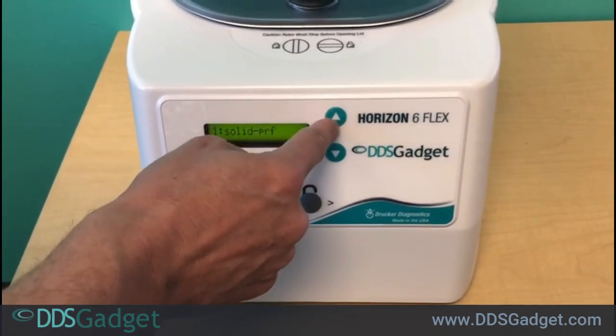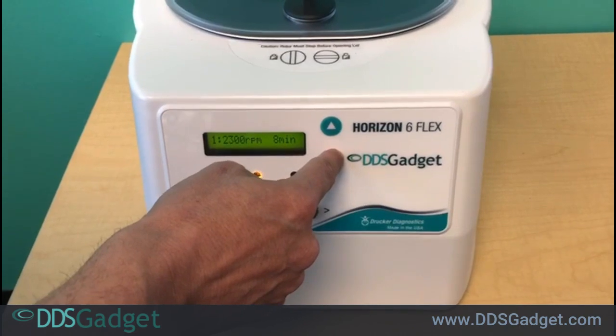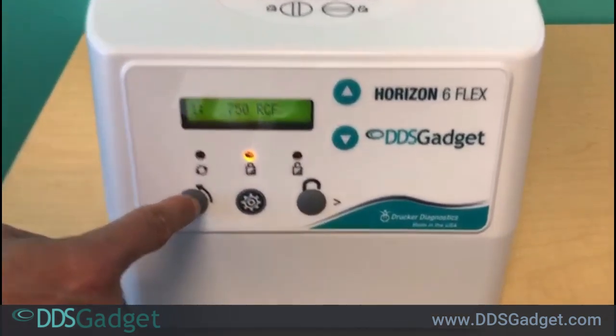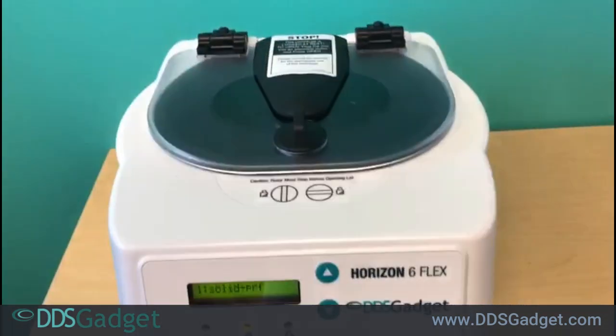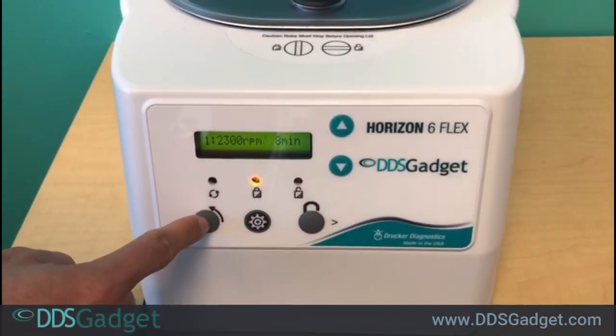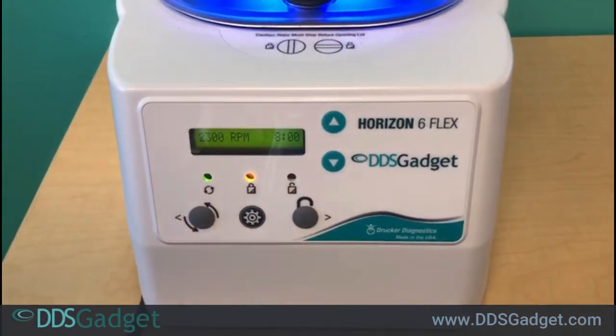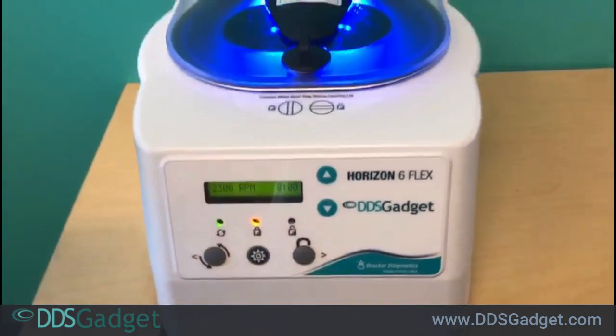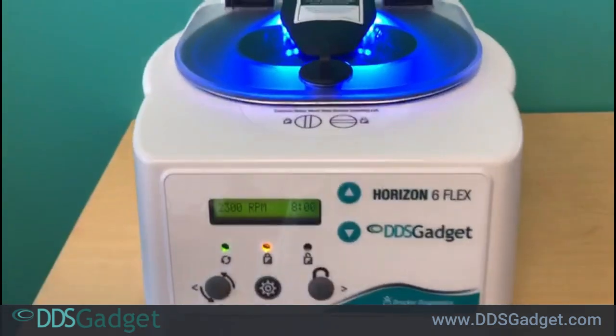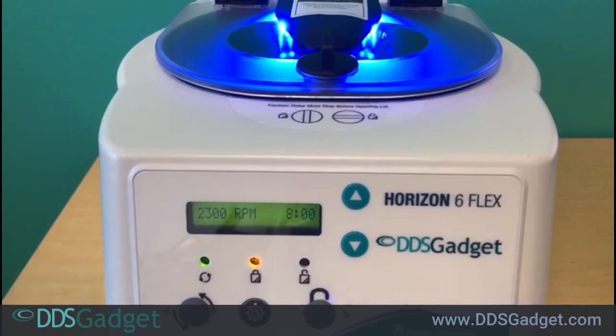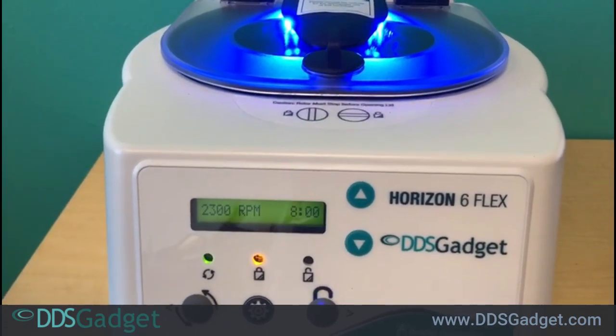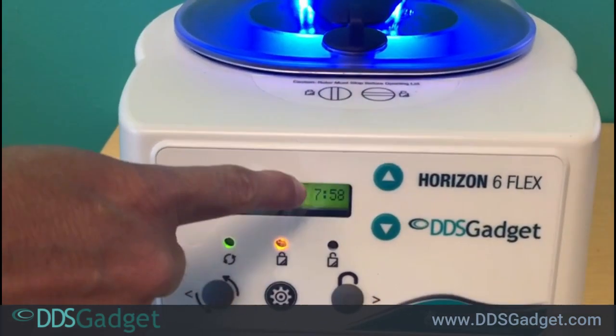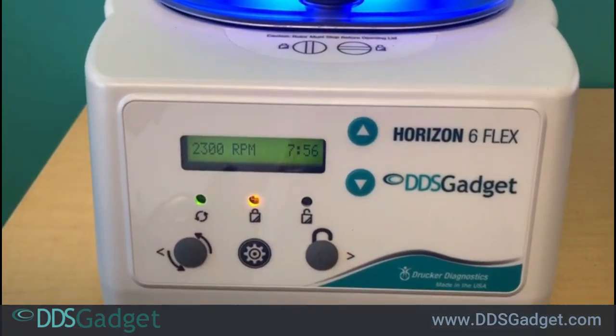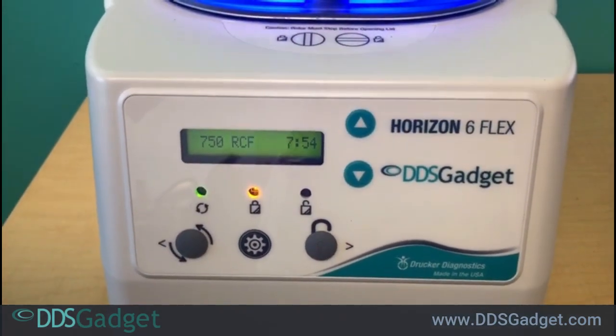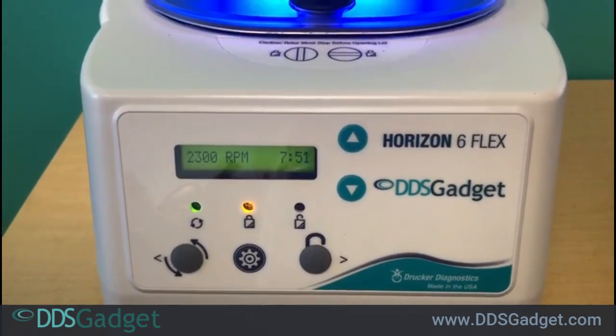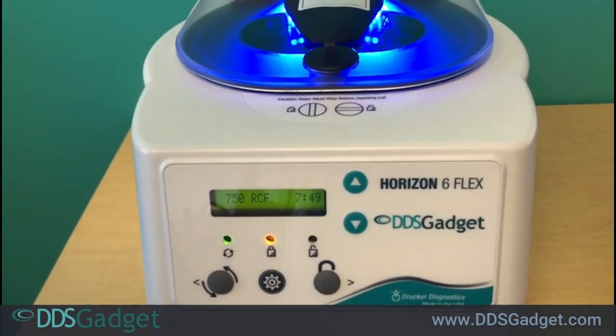Once you actually decide which cycle you want to use, all you need to do afterwards is, again, check to make sure it's locked. You'll have the light on, and then all you need to do is press the start button. The machine then starts to warm up. On a horizontal machine, it just takes some time until the tubes actually reach a horizontal angle on a swing out. Once it starts, you'll see the time start to go down, and then you just have to wait until the cycle ends. There'll be a beep, and you could open the centrifuge, which we'll do in the next video.